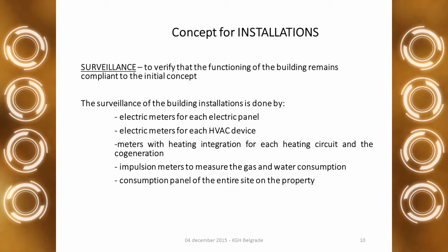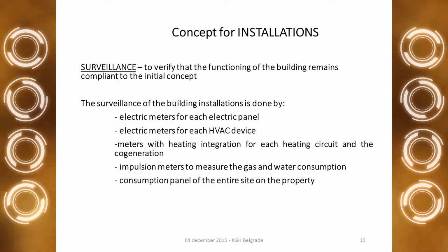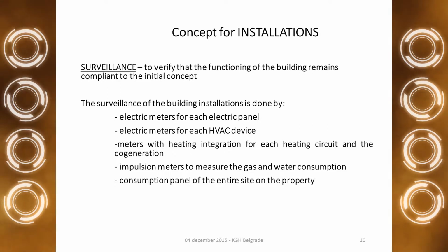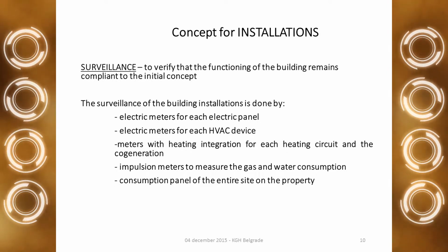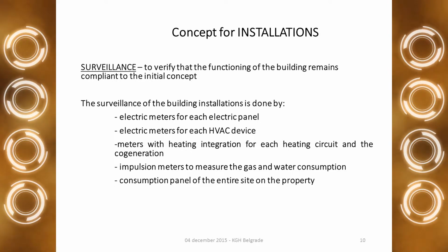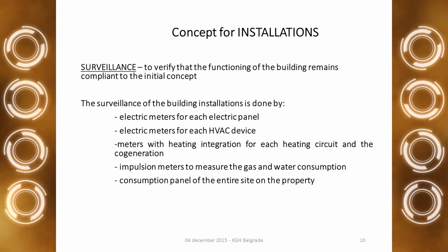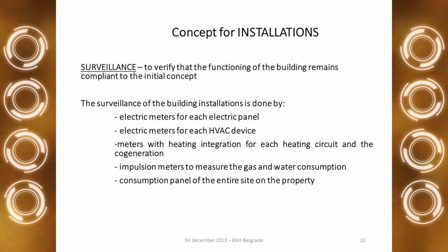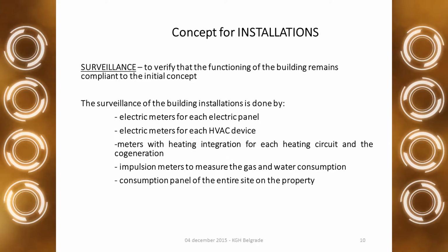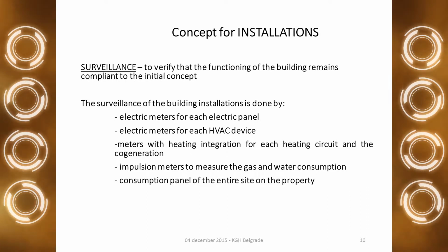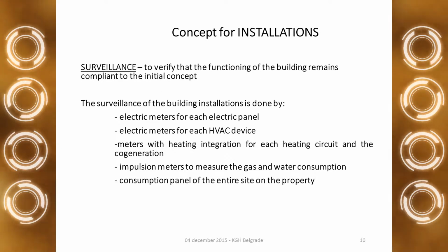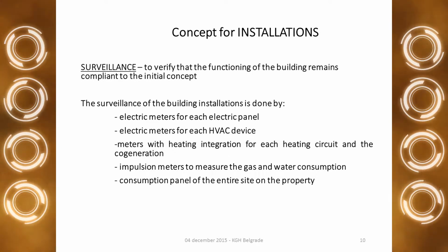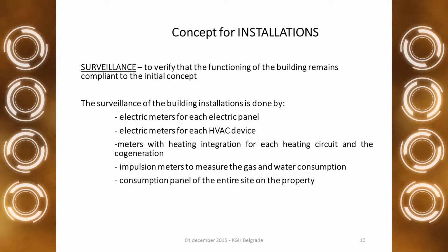The monitoring is an important issue, and it's dedicated to verifying that the functioning of the building remains compliant to the initial concept. The monitoring of the building installation is done by an electric meter for each electric panel, an electric meter for each HVAC device, a meter with heating integration for each heating circuit and the cogeneration, impulsion meters to measure the gas and water consumption, and a consumption panel of the entire site on the property.